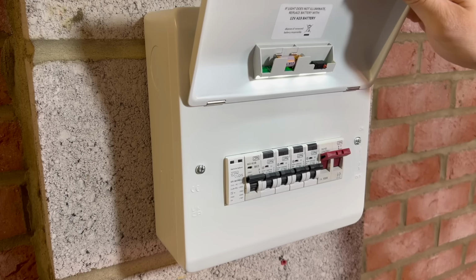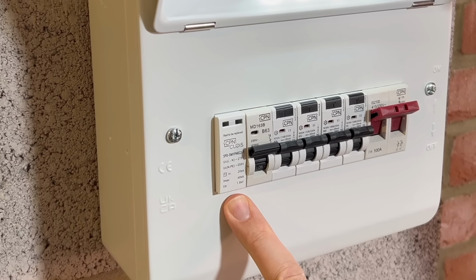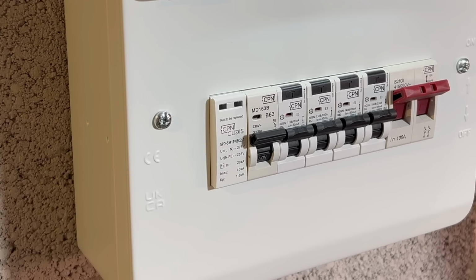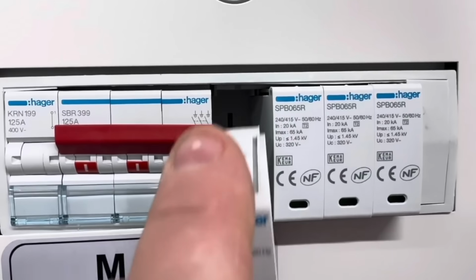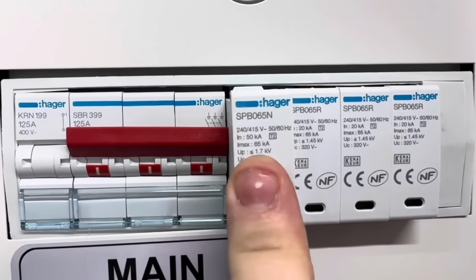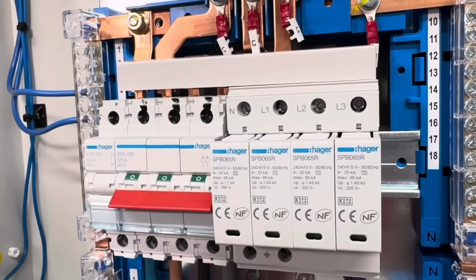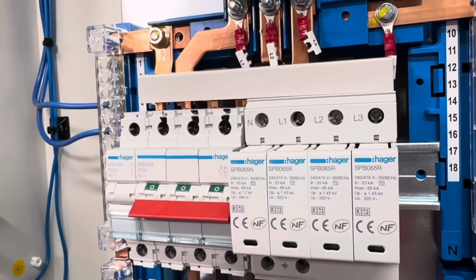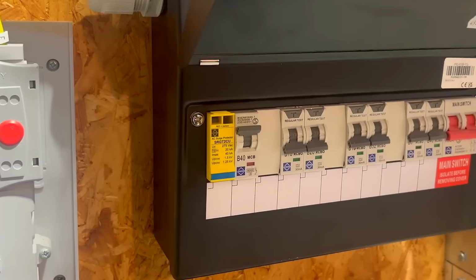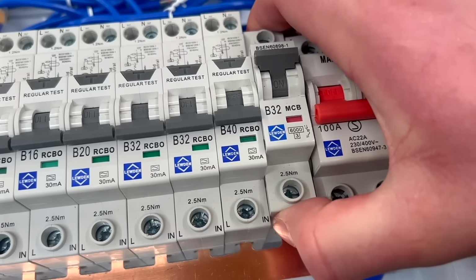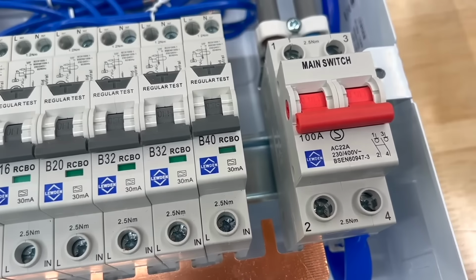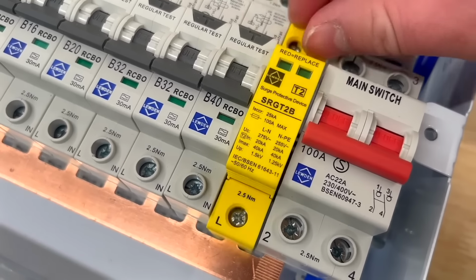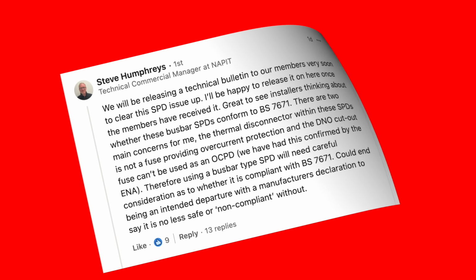A row has erupted in the trade over the use of miniature circuit breakers with surge protection devices in consumer units. The trade is divided over whether units with built-in busbar SPDs and no MCB conform to the wiring regulations. It hinges on whether an absence of an MCB with the surge protection device is a departure from the regs. NAPIT's technical commercial manager Steve Humphreys told LinkedIn this week that the Energy Networks Association has confirmed that the DNO cutout fuse can't be used for overcurrent protection for the consumer side.